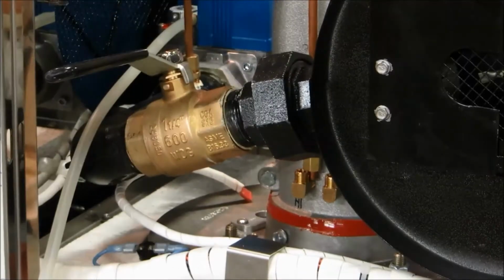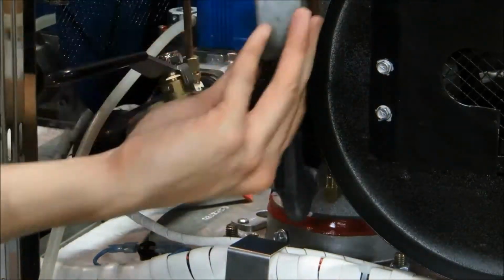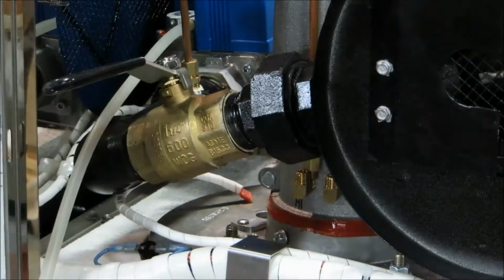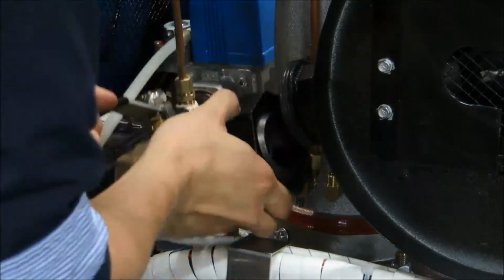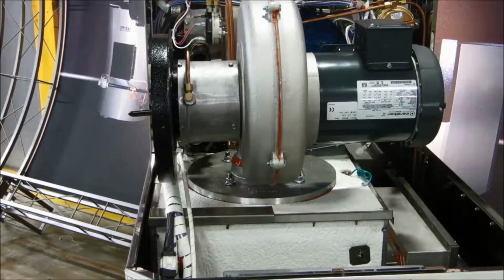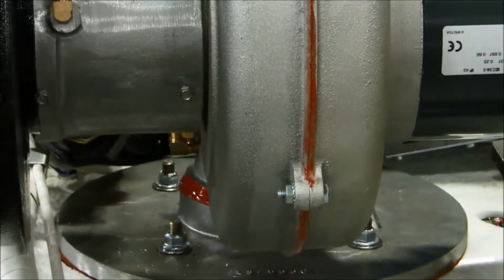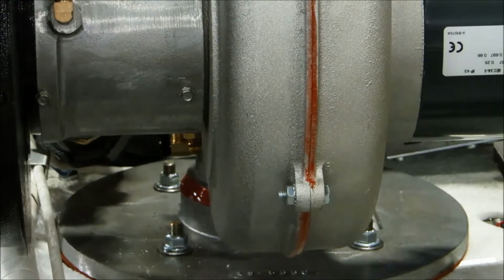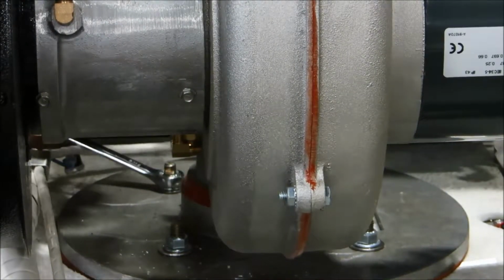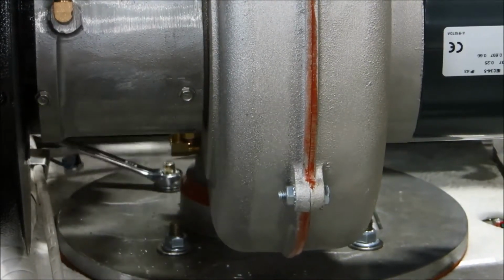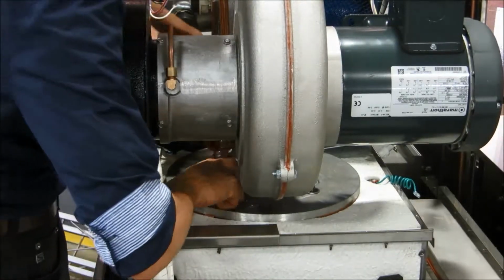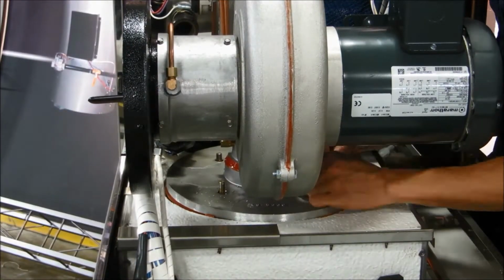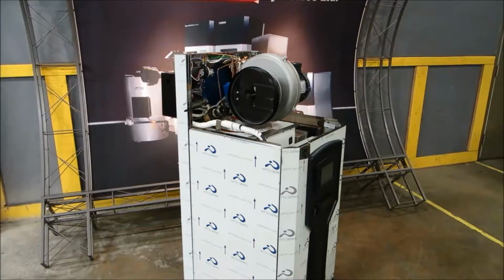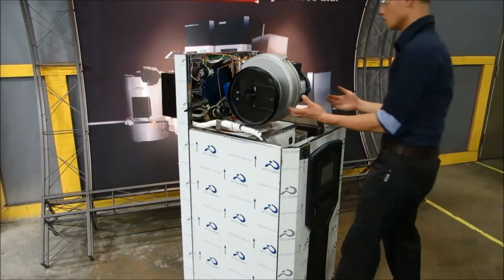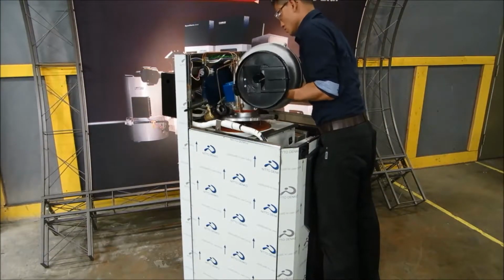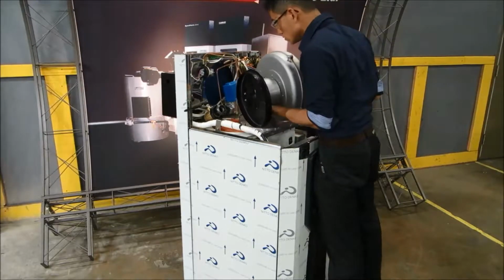Before undoing the union on the gas train, be sure to support the back end of the gas train to prevent it from dropping down. Unplug the harness leading up to the blower. Using a 9/16" wrench, undo the 4 or 8 nuts which fasten the blower to the heat exchanger. The blower motor and blower housing is removed in one assembly. On larger models, you may need assistance to lift it off of the boiler.